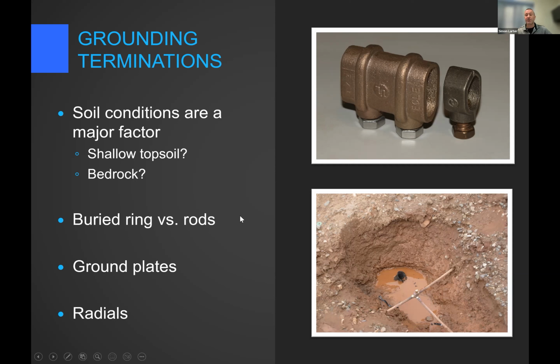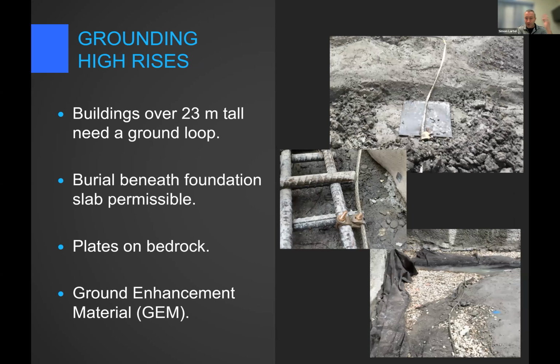Yes, we can do a buried ground ring. We can do a buried ground ring with rods. We can do ground plates. We can do radial grounds, which are just conductors run away from the building in a trench and then backfilled over. We have to do a ground ring on any class 2 structure. So if it's over 23 meters, we must do a ground ring. Didn't used to have to. So older buildings are kind of grandfathered. We're not going to go do a ground ring on a retrofit for a high rise in downtown Calgary or Edmonton. That would be cost prohibitive. But on a new structure, if it's going to be over 23 meters, a class 2 building, we are going to put in a ground ring. Here we go. These are some examples of it.